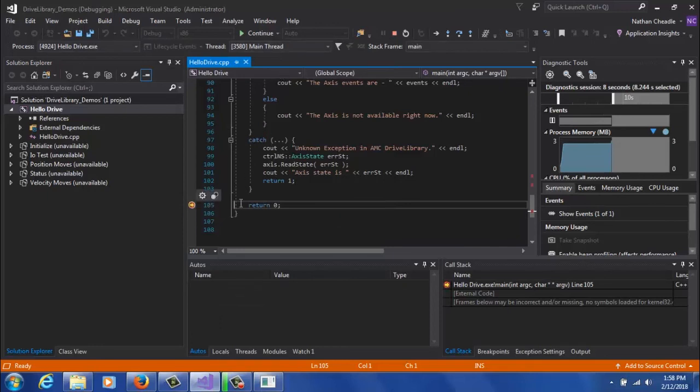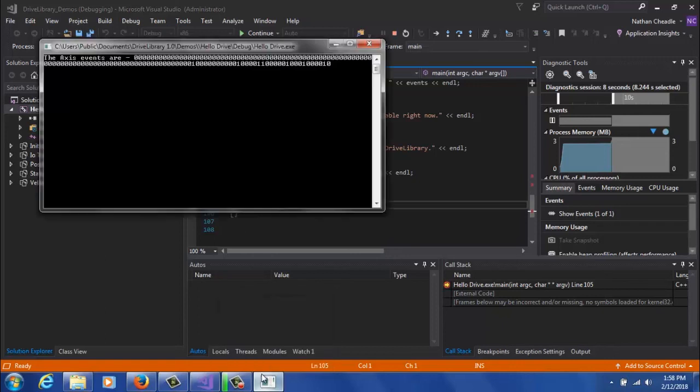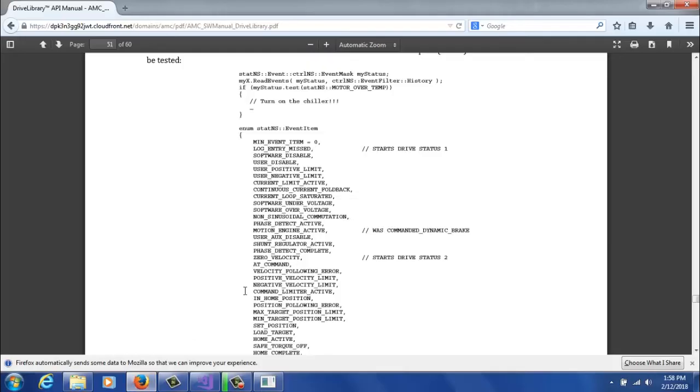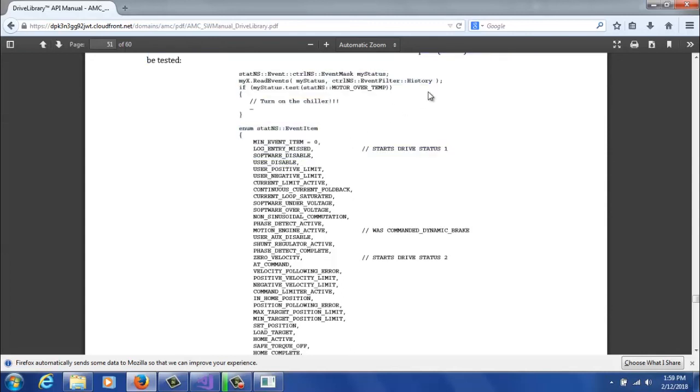You'll want to put a breakpoint at the end so you can actually see these axis events. But when you open them up, you can see it's a number of ones and zeros. Now these don't mean a whole lot to you, but inside of our manual in Appendix E, there is a list of all the events. So for example, if bit 3 was high, that would be user disable. That would mean that the user disable was one of the active events.